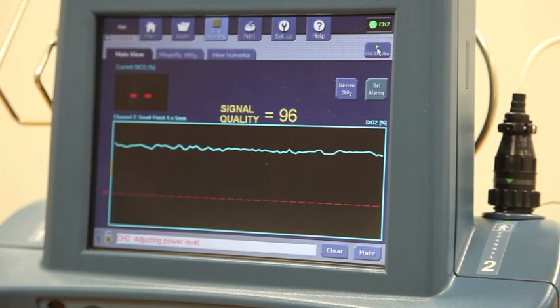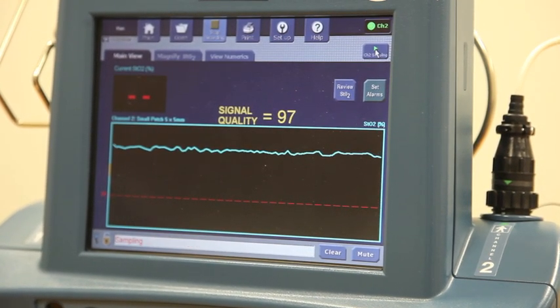Each sensor requires a few moments to adjust to the light level as indicated at the sampling status shown in the message line on the bottom of the screen. When the sensor is done calibrating, a signal quality number will appear. This number is an indicator to guide you in positioning the sensor for reliable StO2 readings. Remember, the ideal range for signal quality is above 80. When signal quality reaches a satisfactory range, the current real-time reading of tissue oxygen saturation percentage, StO2, will display.